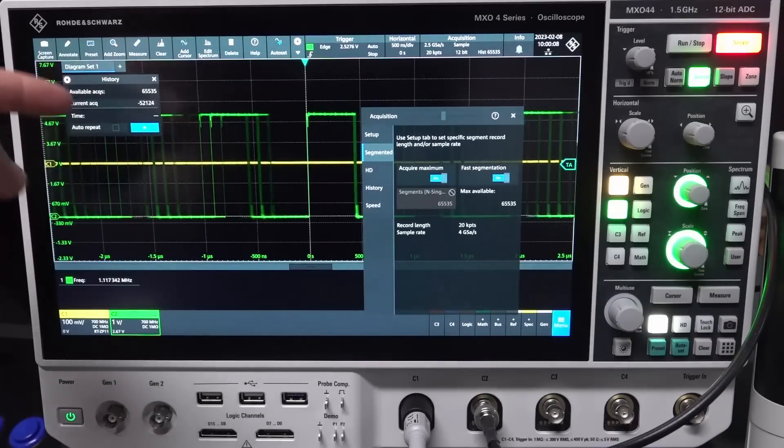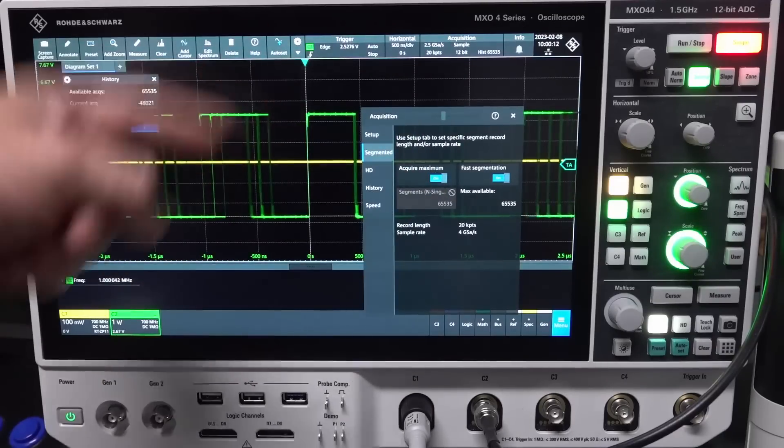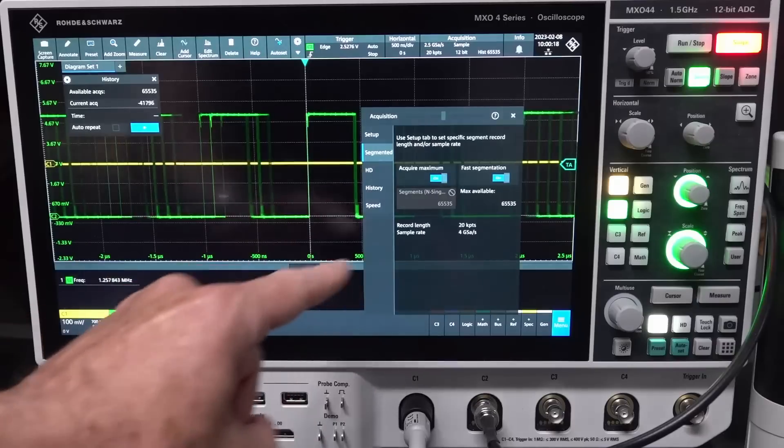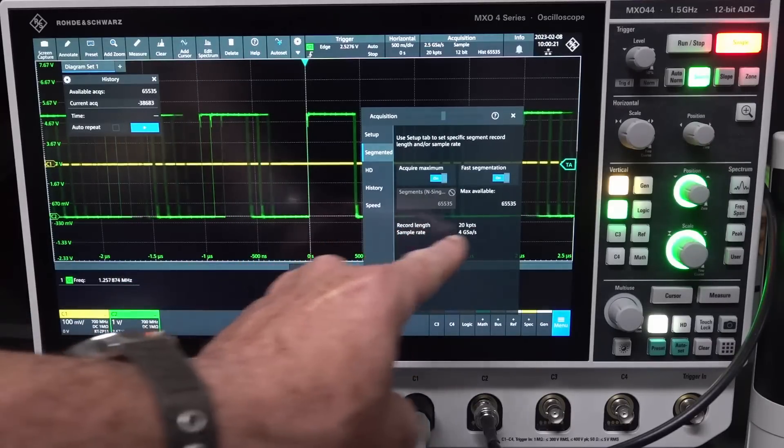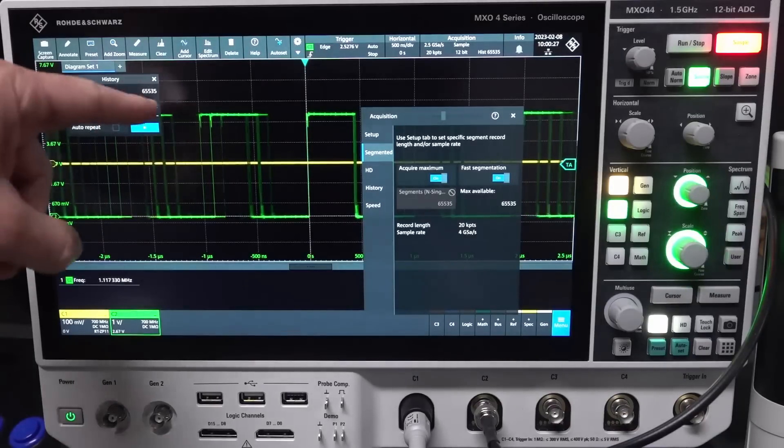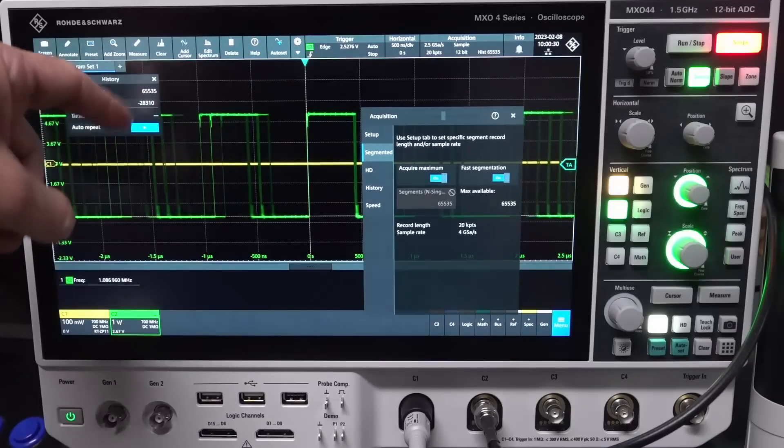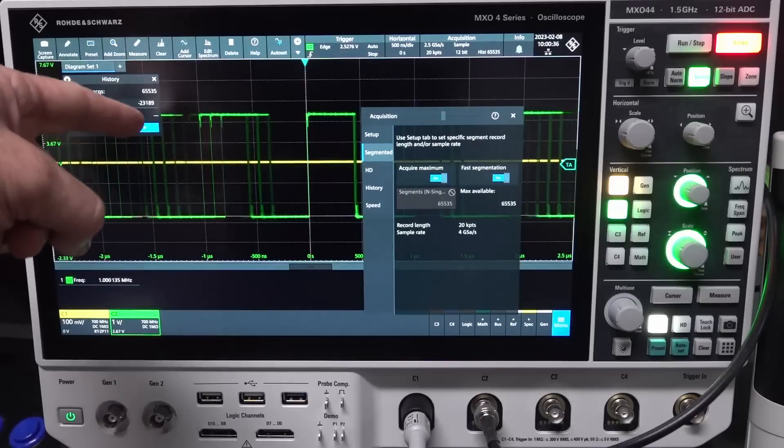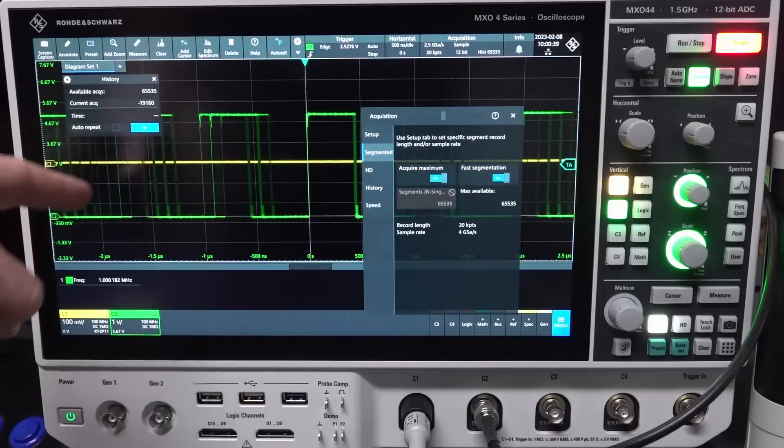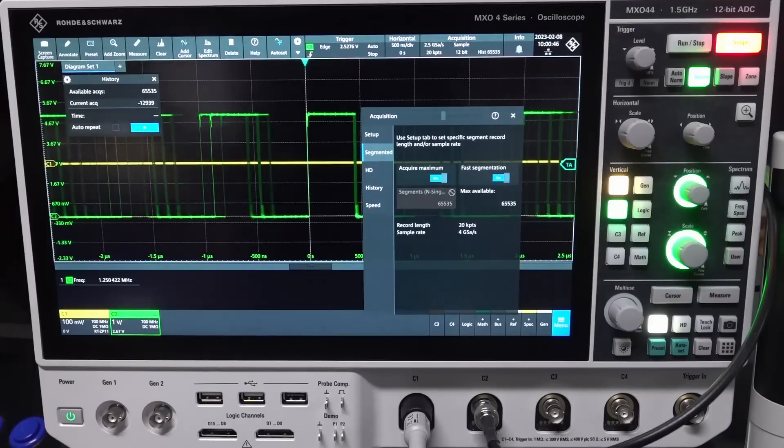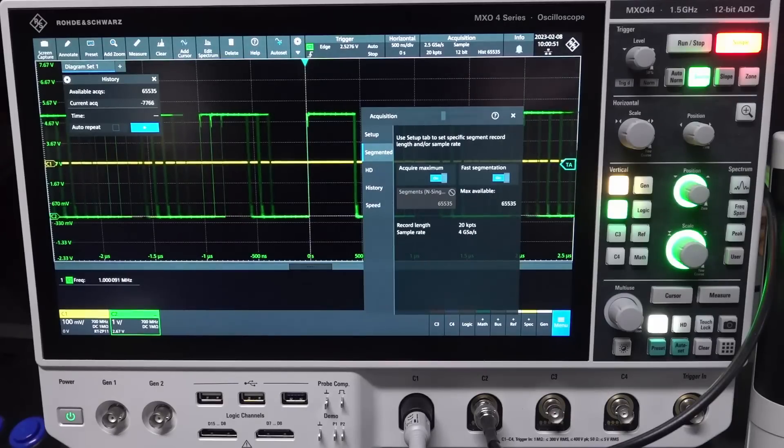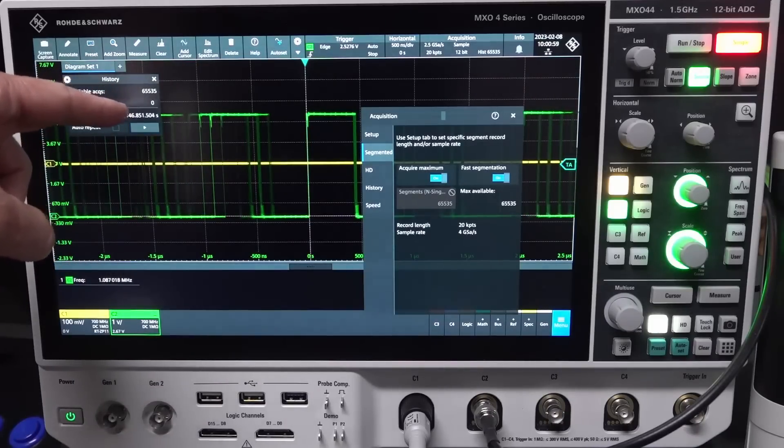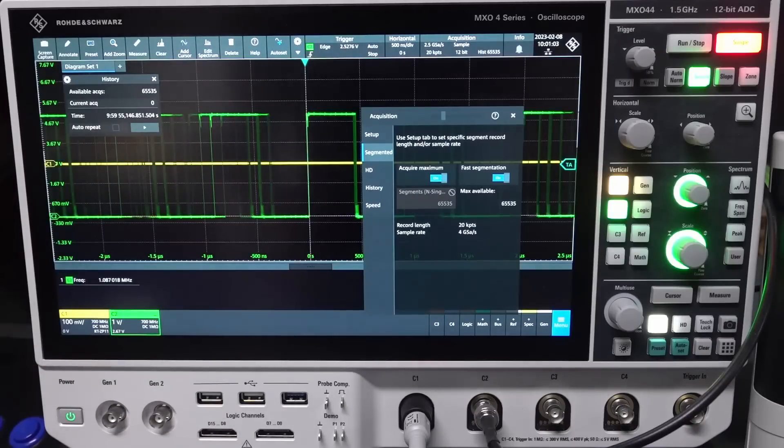So you can actually press single shot capture, set it up, press single shot capture and depending on your waveform update rate, you can, and you can set a delay in that as well. Yeah, record length, there you go, that's why they tell you the record length, 20K points, 4 gig samples. So it's only, it doesn't tell you the, it'd be nice if it told you up there what the waveform acquisition, but I guess you can tell by just looking at it. So yeah, it will, I'm pretty sure when it gets down to zero it will stop there. So that's really cool. You can, if you're trying to debug something, you can set it up and then you know, it might come in the next 10 minutes or whatever, then you can just press your single shot, you can walk away, come back, and stop. Yes, there we go. We got it.